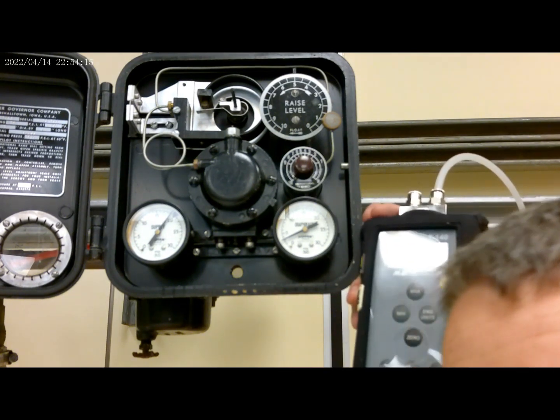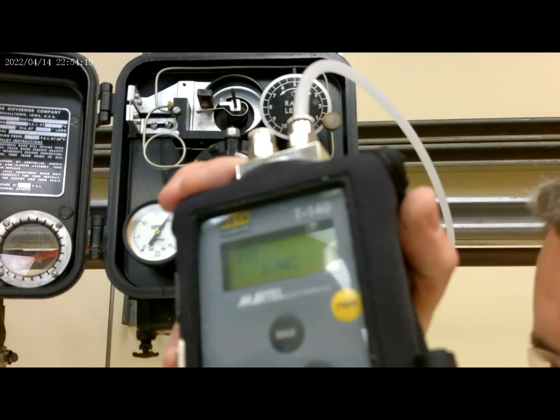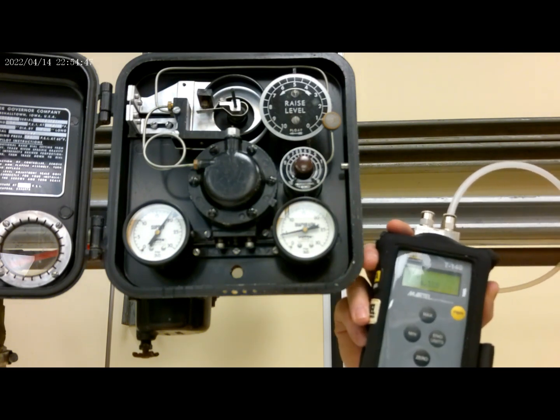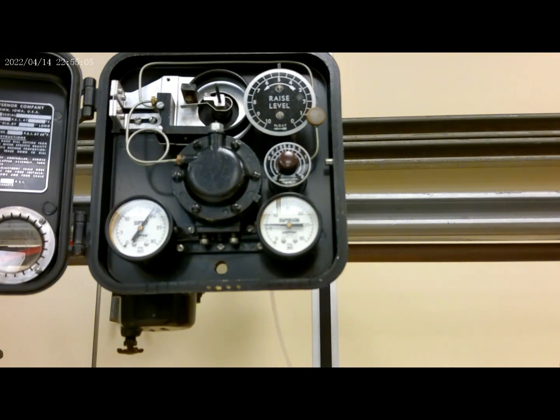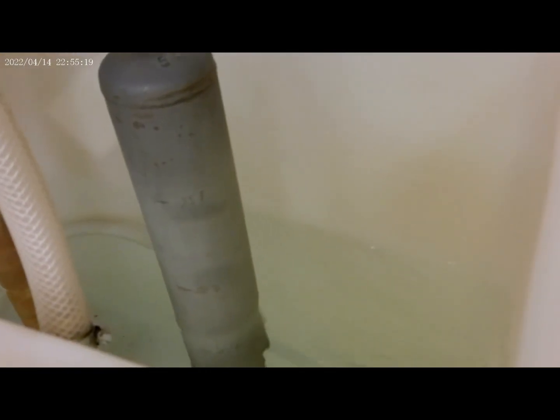Okay, so here we have 3 psi. I'm going to increase the water level, and that's going to allow the water to rise. As the water rises, it's going to bring our output up. I know you can see this output a lot better than you can see this one. This one is at 4 psi right now. As the water level rises, you're going to see the pressure output rise. There are markings on the displacer. You see the water rising now, we're past 25%.